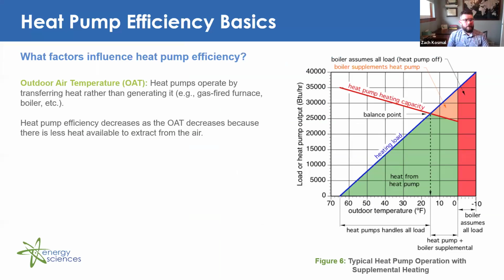So, what factors influence heat pump efficiency? One of the largest and key drivers of this is your outside air temperature. Okay. So heat pumps operate by transferring heat rather than generating it. And I just touched on how those COP values can be much higher than electrical resistance, for example. And that is the reason right there. Heat pumps do not generate heat, they transfer it. Whether that medium be your outside air for an air source heat pump or groundwater for a water source heat pump, the purpose is transferring that heat rather than generating it. So heat pump efficiency decreases as the outside air temperature decreases as well. This is because there's less heat available to extract from the air.